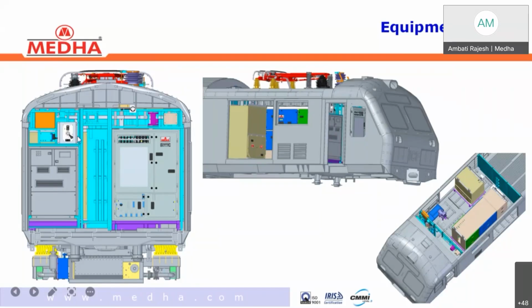And just next to that, this is the DC earthing switch and here the AC earthing switch and headlight converter; these are all we can find. And from side view, if we see, just back to the driver cabin, this is the HT compartment. Here, this one is the auxiliary converter and this side the traction converter. The same from top view, we can find here the bigger unit, this one. When we enter into the HT compartment, the right side bigger unit is the LTC, 1300 kVA line and traction converter, air cooled converter. And the left side, 120 kVA rating auxiliary converter unit. Both are from MEDHA. And here there is a small compressor, the auxiliary air compressor or baby compressor, to provide the pneumatic supply to the pantograph.